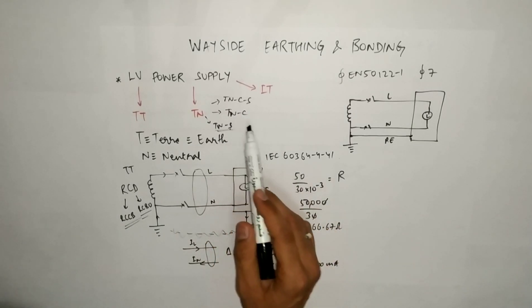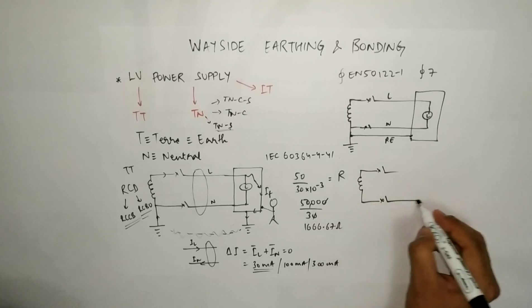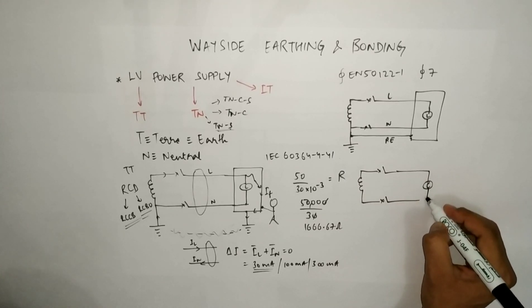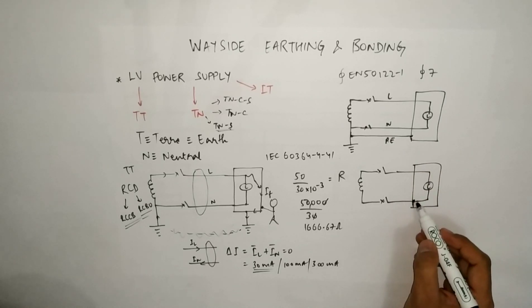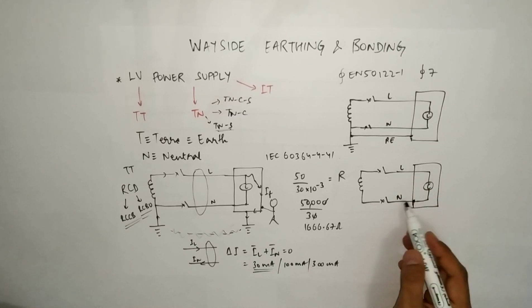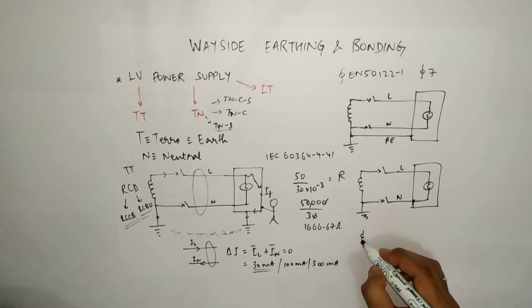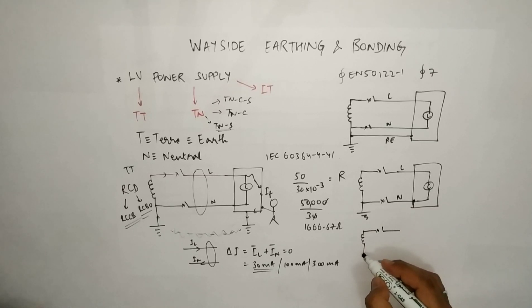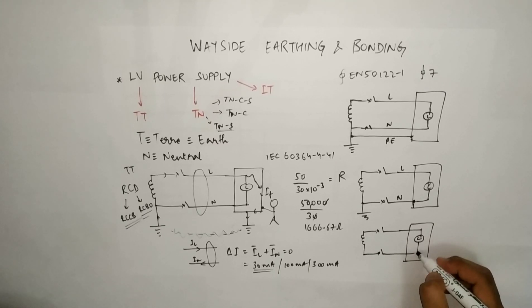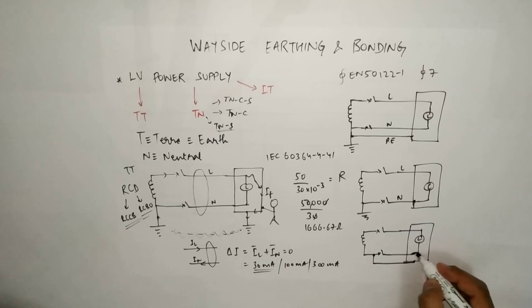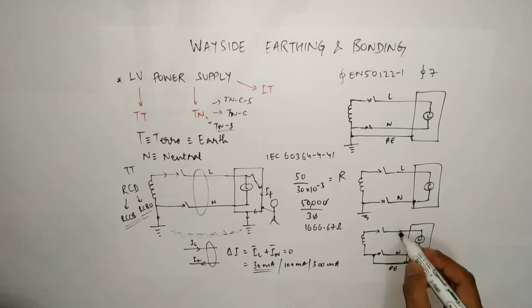For TNC, it is earth and neutral combined. The source feeds line and neutral to the load, and the earth conductor also acts as neutral — both are the same conductor. In the case of TNCS, for some portion the neutral and earth are the same, and later there is a dedicated conductor connected to the earth. Up to that split point it is TNC, and from there it becomes TNCS, where the PE conductor and neutral are separate.